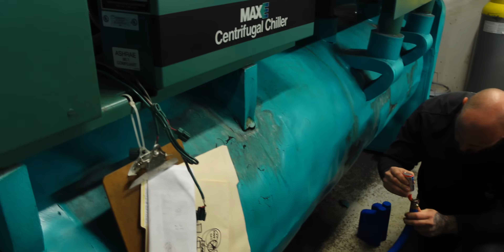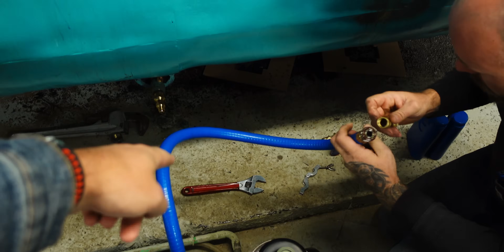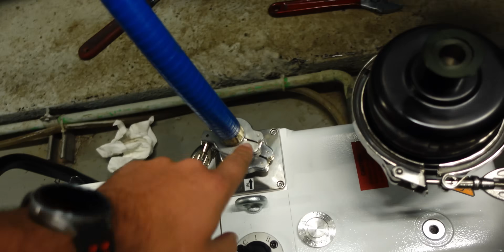This is where I'm really interested to see, because this is what this pump was really made for. We've got around a 350 ton centrifugal that holds 1,500 pounds of charge, and we're going to hook up a half-inch connection, 3/4 inch ID hose coming off the drain port on the bottom, and pull down. We've got our BluVac set up, testing it against the JB this time, just out of curiosity. So we have a half-inch connection feeding into the blue hose, coming into the KF16 fitting, which is then adapted to a KF25.